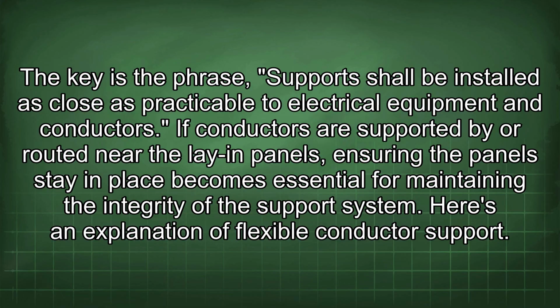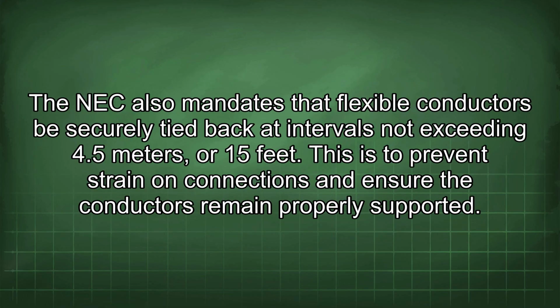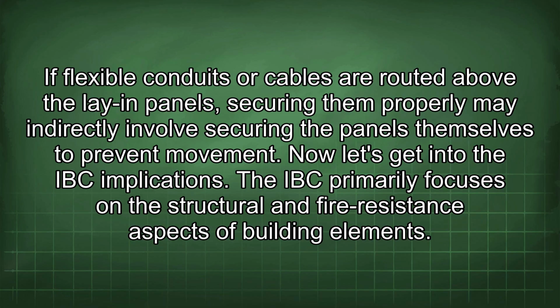Here's an explanation of flexible conductor support. The NEC also mandates that flexible conductors be securely tied back at intervals not exceeding 4.5 meters or 15 feet. This is to prevent strain on connections and ensure the conductors remain properly supported. If flexible conduits or cables are routed above the lay-in panels, securing them properly may indirectly involve securing the panels themselves to prevent movement. Now let's get into the IBC implications.